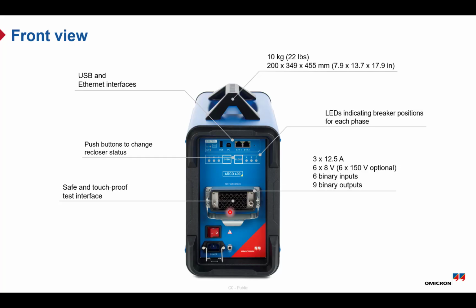so you don't accidentally touch them. Now, in terms of the outputs, the ARCO 400 can inject 3-phase currents and up to 6 voltage signals. For current, it provides up to 12.5 amps per phase, which is suitable for recloser applications due to the typical CT ratios used.